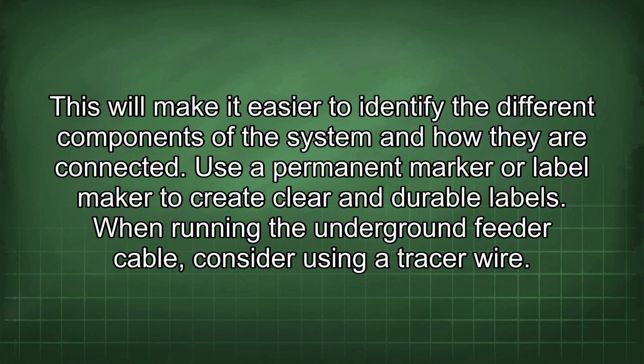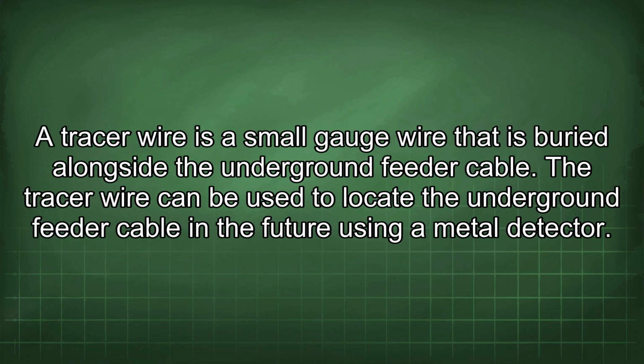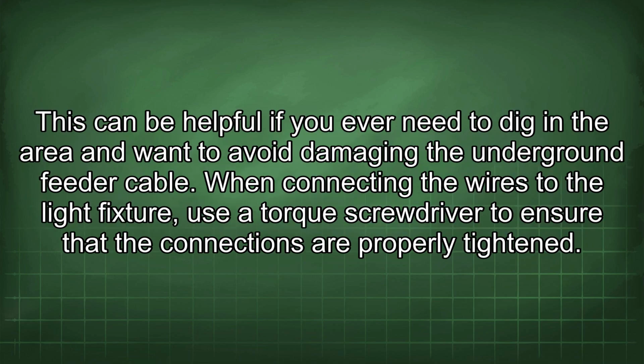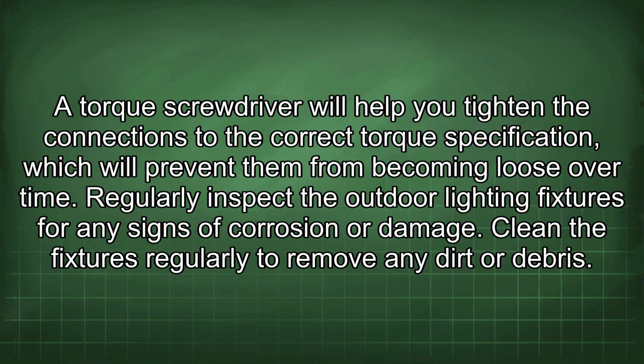When running the underground feeder cable, consider using a tracer wire. A tracer wire is a small gauge wire that is buried alongside the underground feeder cable. The tracer wire can be used to locate the underground feeder cable in the future using a metal detector. This can be helpful if you ever need to dig in the area and want to avoid damaging the underground feeder cable. When connecting the wires to the light fixture, use a torque screwdriver to ensure that the connections are properly tightened. A torque screwdriver will help you tighten the connections to the correct torque specification, which will prevent them from becoming loose over time.